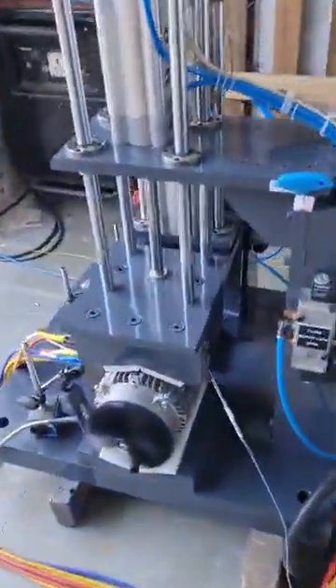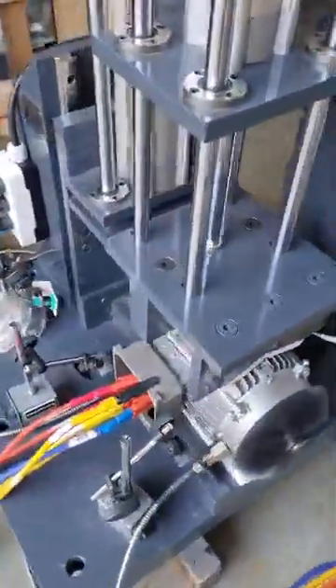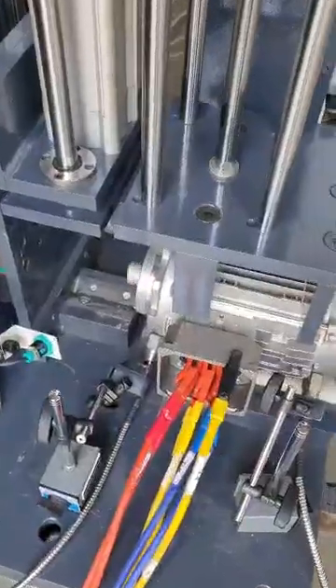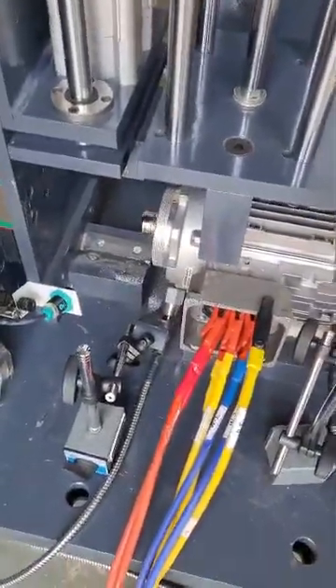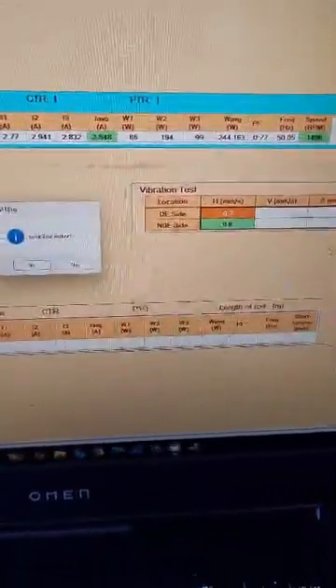voltage test. You can see some noise coming over here, that's the motor running. Okay, motor running, you can see it over here, and everything gets captured automatically. And the no load test is all the measurements, you can see it over here, whether it is the percentage of voltage applied, various voltages, average, the current, and everything that you see. And then we have the next test, that's vibration test, for which that is also done.